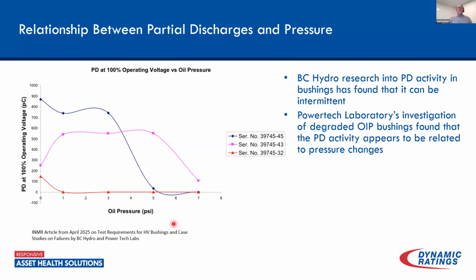The other thing that happens is with the expansion and contraction that we talked about. Basically, as we're adding load, we're driving the temperatures up, and the oil expands, and we're increasing and decreasing the pressure within both the transformer and the bushing. As the temperature increases, the oil expands, and that also has an impact on the partial discharge activity.